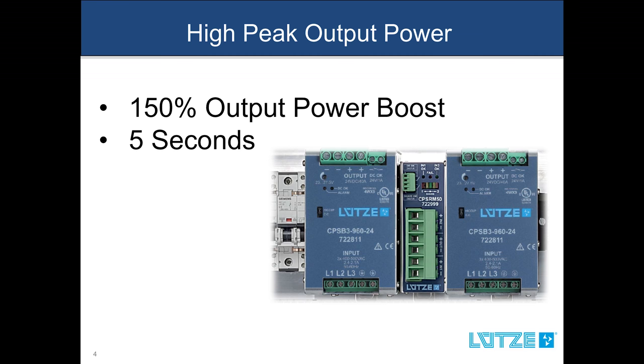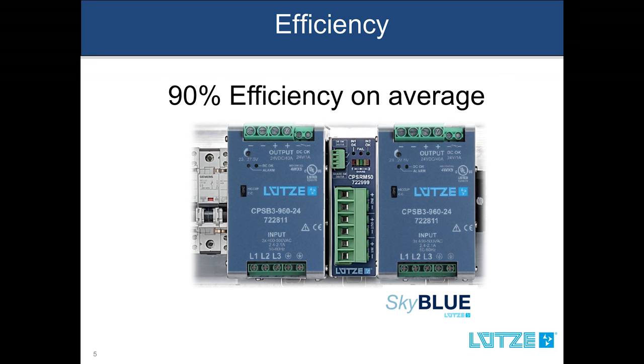Secondly, there are differences in the electrical characteristics. While both series provide reliable performance, the compact series is intended for more robust applications. The compact series single, two, and three phase units have high peak output power capabilities, which eliminate the need to oversize your power supply for high inductive or capacitive loads. The compact series provides an operating efficiency of greater than 90% on average, thus reducing the amount of unwanted heat dissipation.